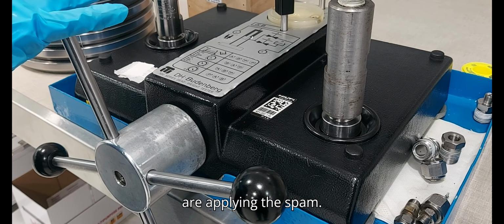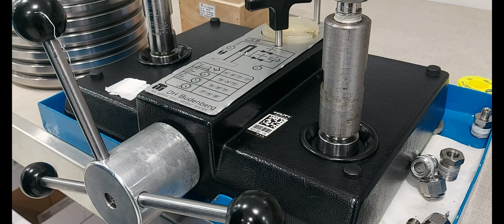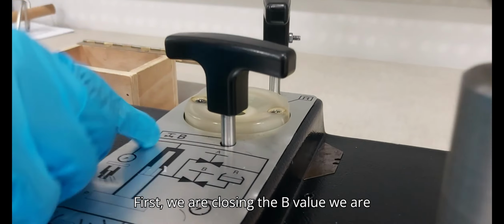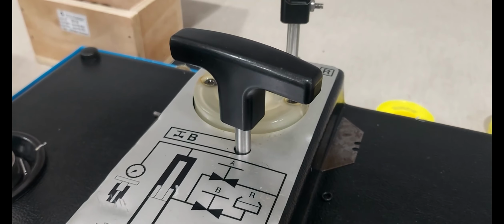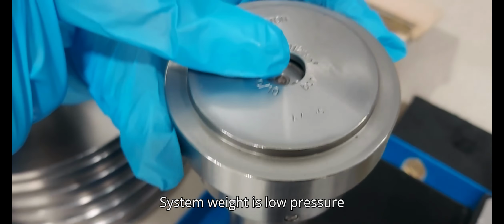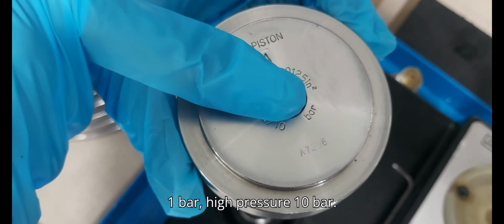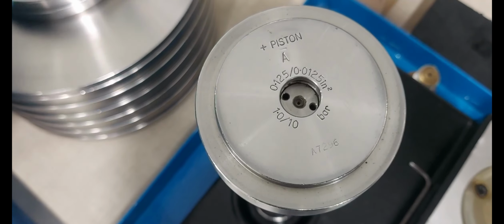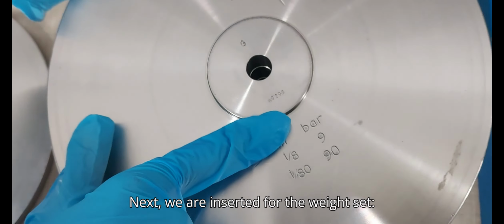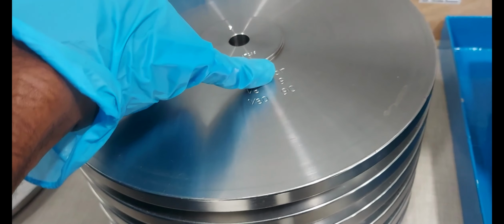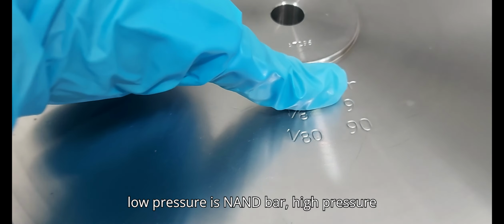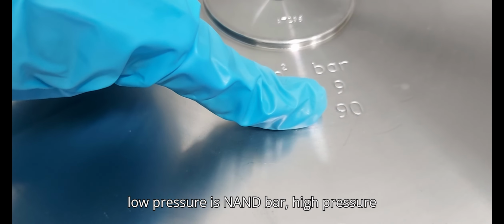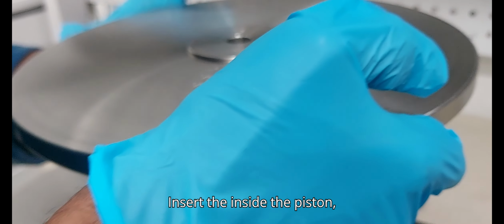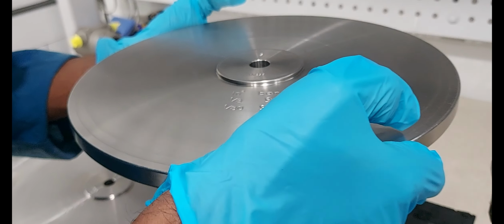Next we are applying the span. First we are closing the B valve. The system weight is low pressure 1 bar, high pressure 10 bar. Next we insert the weight set. Low pressure is 9 bar, high pressure is 19 bar. Insert it inside the piston.